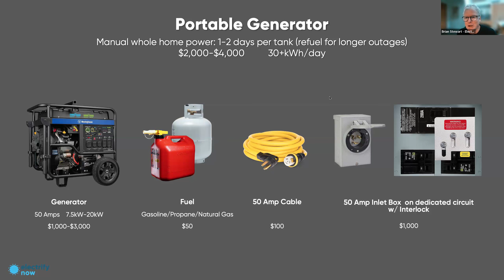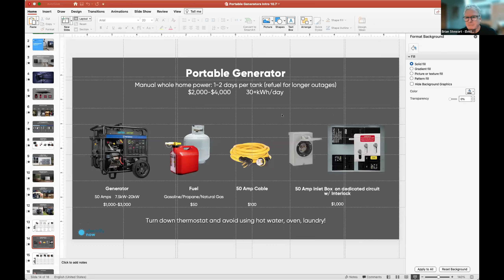This is a really slick solution, just so people understand. This is the main breaker here, so you can turn off the whole panel. Essentially, this little mechanical thing means you can't turn on the breaker to the generator, which is this one here, unless the main breaker is turned off. Then you can slide this thing up and turn the circuit breaker on for your generator. So there's no way you can have your generator putting power into your panel and have the main breaker on. It's a pretty ingenious little device that makes this relatively inexpensive to connect to the main panel.